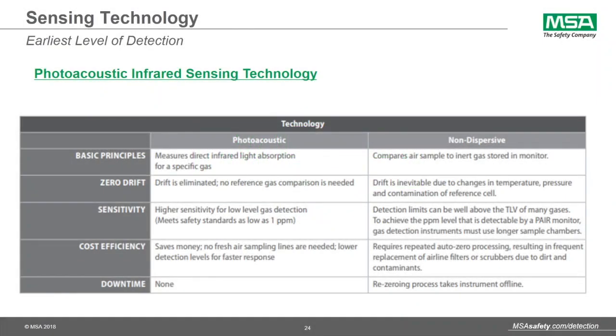There are other technologies on the market, and they include semiconductor and non-dispersive infrared. I have a chart here comparing the two infrared technologies. So for basic principle, photoacoustic measures direct infrared light absorption for a specific gas, whereas non-dispersive actually compares an air sample to inert gas that's stored in the monitor.